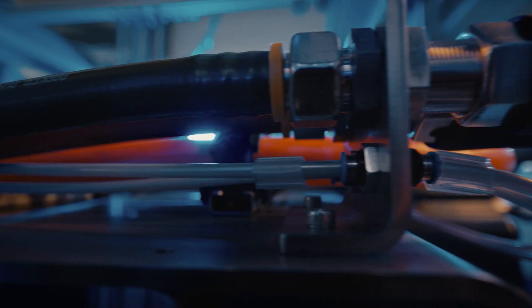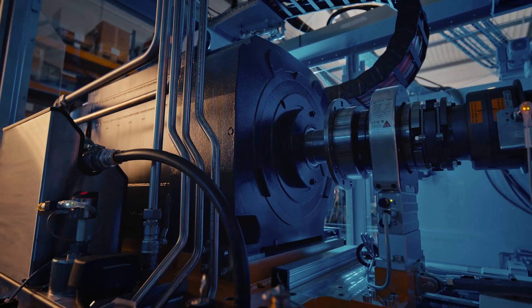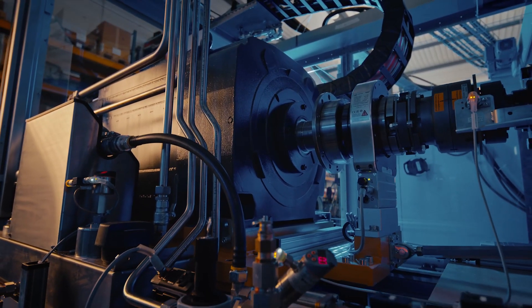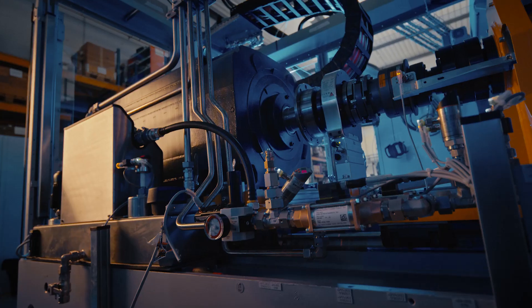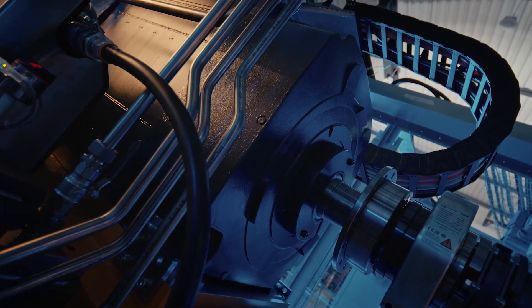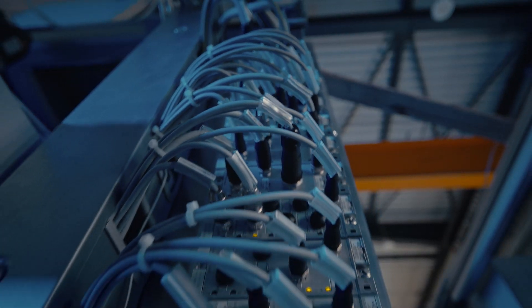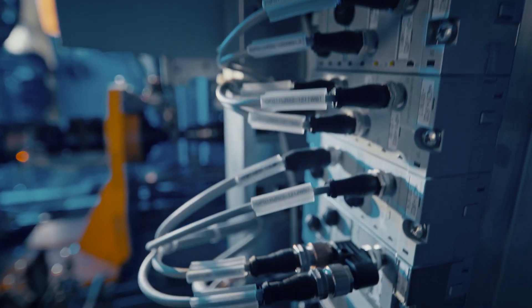For our customers, we work with the existing infrastructure with a 400-volt input voltage. With the Siemens solution — with the DCPs — it's then raised to a DC link voltage of 850 volts. This means we don't have to make any additional investments in infrastructure; for example, we don't need any larger transformers for 850 volts, which would also mean thicker cable. And we only need energy for accelerating — we keep energy from braking in the DC link, so that it doesn't put an additional load on the power supply.